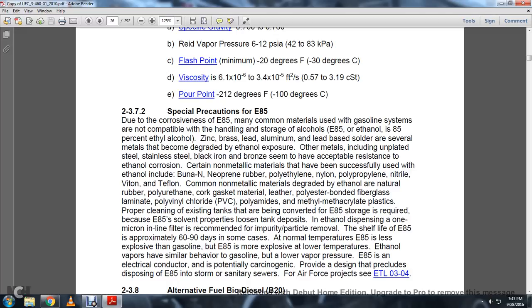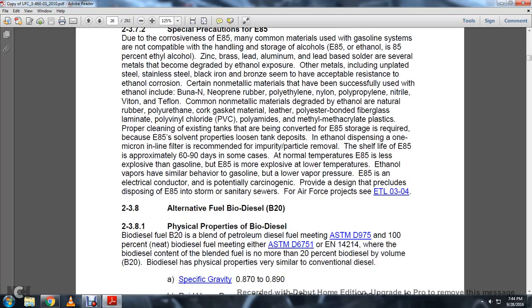Methyl methacrylate plastic is also affected. Cleaning of existing tanks being converted to E85 storage is required, because E85 acts as a solvent and loosens tank deposits. A 1 micron in-line filter is recommended for impurity particle removal. The shelf life of E85 is approximately 90 days. At normal temperatures E85 is less explosive than gasoline, but E85 is more explosive at lower temperatures. Ethanol vapors behave similarly to gasoline vapors but have lower vapor pressure. E85 is an electrical conductor and potentially carcinogenic. Provide a design that precludes disposing of E85 in storm or sanitary sewers. For Air Force projects, see ETL 03-04.